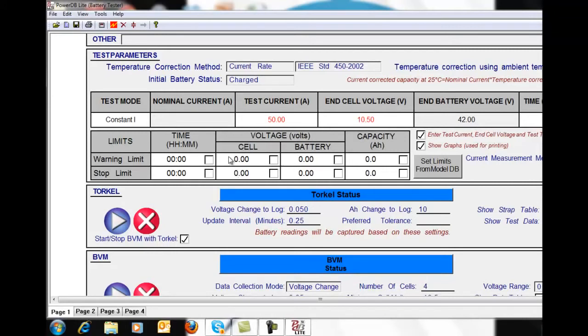I also can go ahead and put in warning and stop limits. For instance, I may put in a warning limit and say, well, when the battery bank gets down to 11 volts per jar, I want to be notified. When the battery bank gets down to 10.5 volts per jar, I want the test to end.